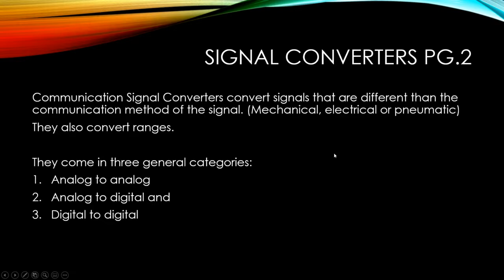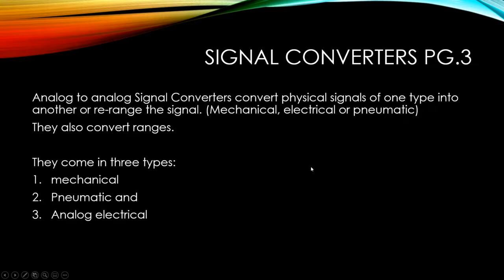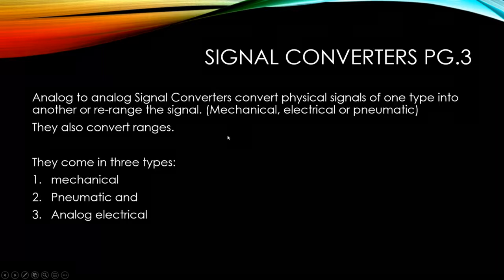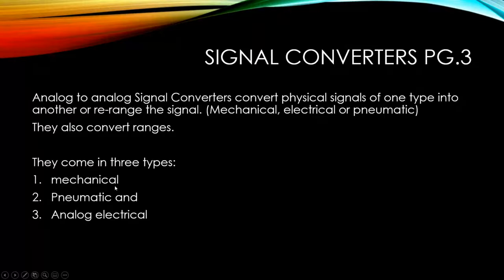Signal converters convert signals that differ from the communication method of the signal, and they also convert ranges. They come in three general categories: analog-to-analog converters, analog-to-digital converters, and digital-to-digital converters. Analog-to-analog signal converters convert physical signals of one type into another — whether mechanical, electrical, or pneumatic — and they can also re-range or convert ranges. Analog converters come in three basic types: mechanical, pneumatic, and analog electrical.